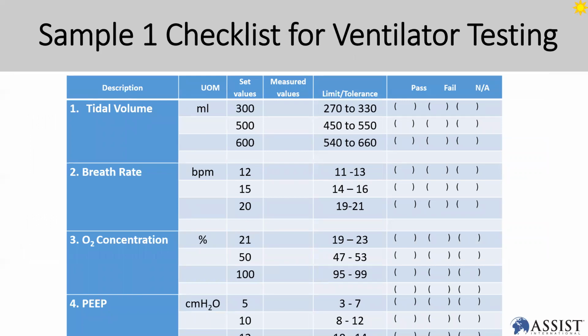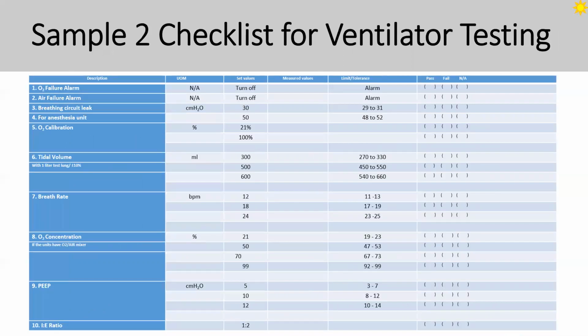For ventilator testing, you need to monitor tidal volume, breathing rate. So you need to set, for example, 300, and you need to see the output reading on the tidal volume, breath rate, PEEP, O2. Another one is IE ratio. This is a very important parameter that you're going to test. Sample of the second checklist is almost similar, but the only thing is you're going to do some calibration on O2. Then you have IE ratio and alarm test. You're going to test with the test lung, all that.